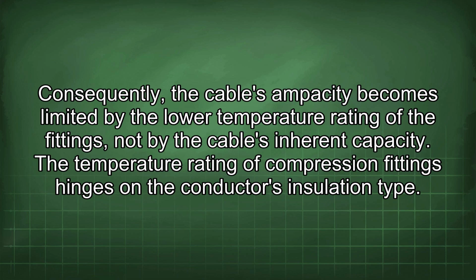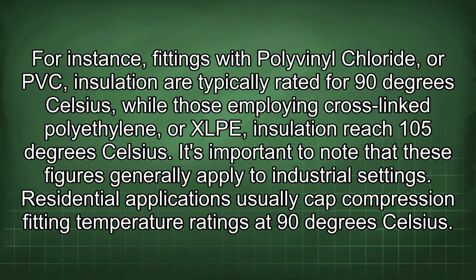The temperature rating of compression fittings hinges on the conductor's insulation type. For instance, fittings with polyvinyl chloride, or PVC, insulation are typically rated for 90 degrees Celsius, while those employing cross-linked polyethylene, or XLPE, insulation reach 105 degrees Celsius. It's important to note that these figures generally apply to industrial settings. Residential applications usually cap compression fitting temperature ratings at 90 degrees Celsius.